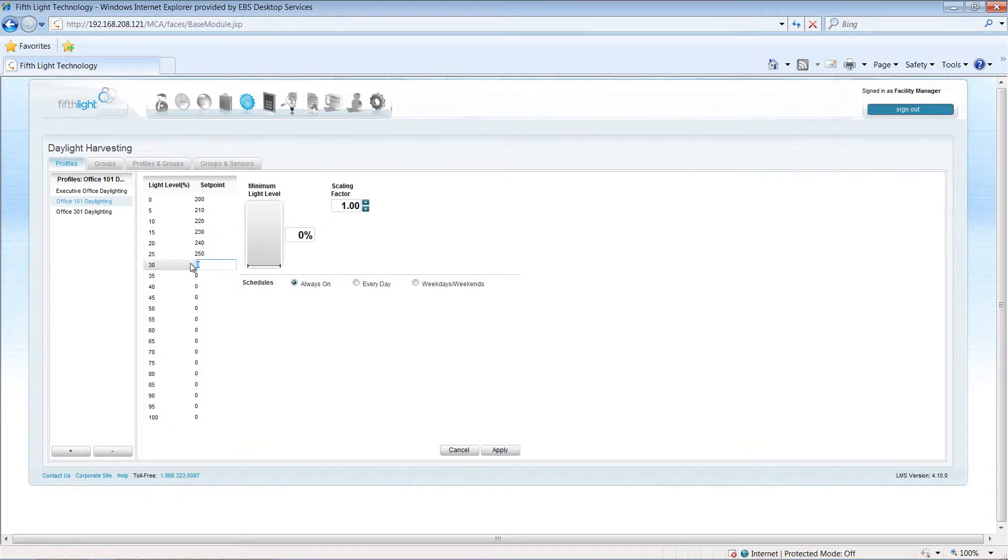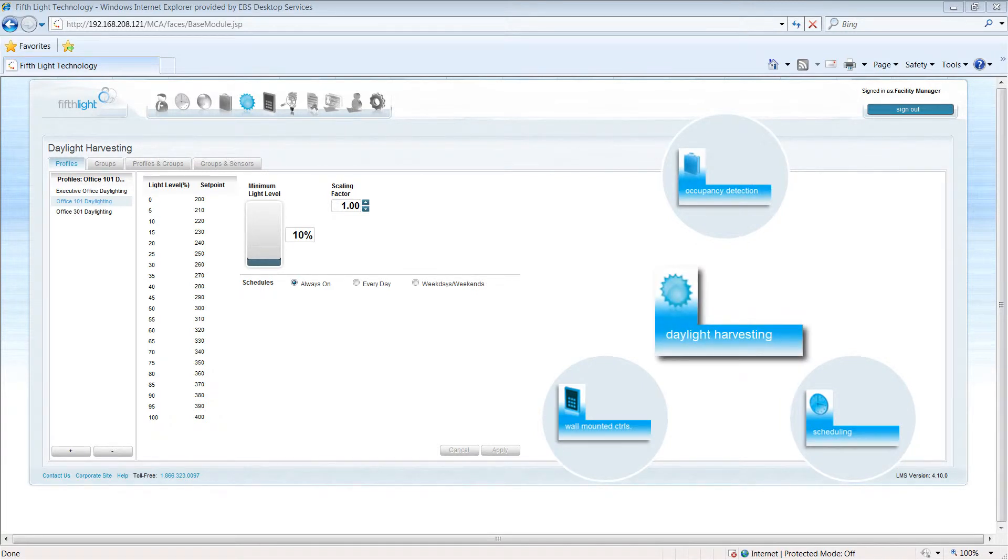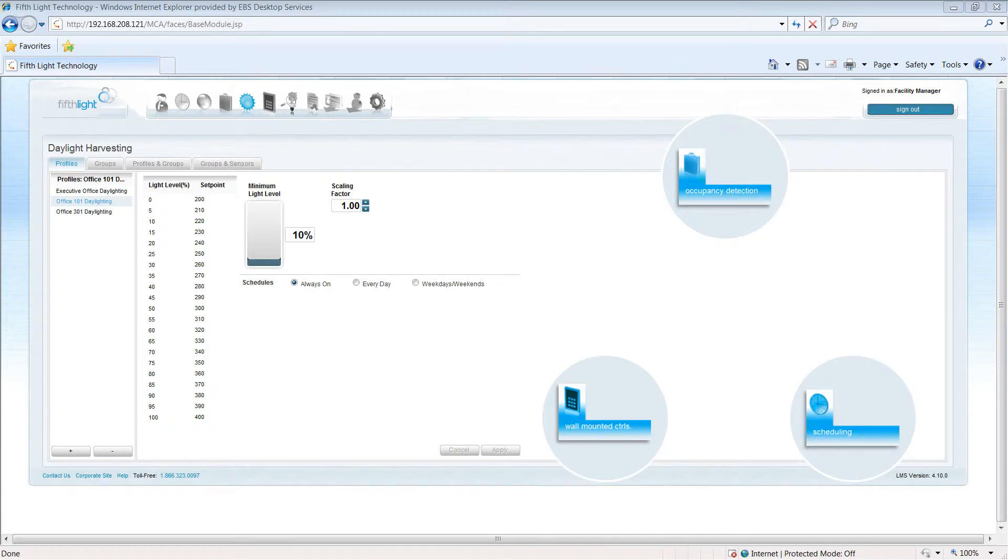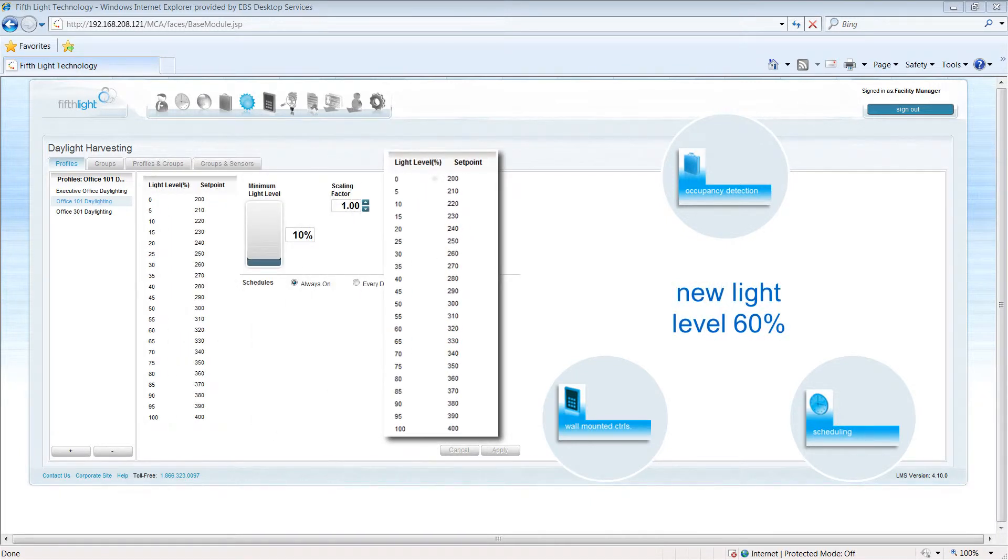The fifth light system manages the interaction of other control strategies along with the daylighting profile. When a wall-mounted control, occupancy sensor, or schedule requests a light level change, the system looks at the daylighting profile and adjusts the electric light according to the set point for the called level.